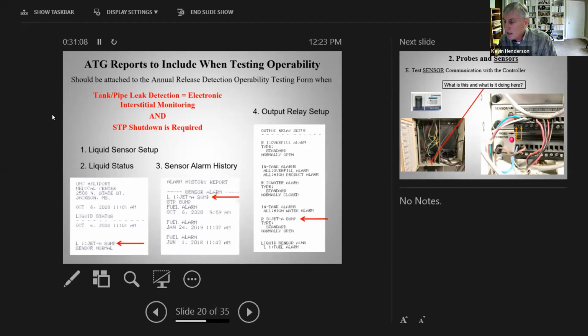So those are what they call this low-level testing. And basically what that means is you only have to test the bottom few inches of the sump as long as you have sensors in that sump that will cause the STP to shut down if they go into alarm. So if you have a place that you're testing and they're doing low-level testing, you need to understand that. You need to be able to show that you did make the sensors go into alarm, but you also need to be able to show that those alarms will in fact shut down the STP.